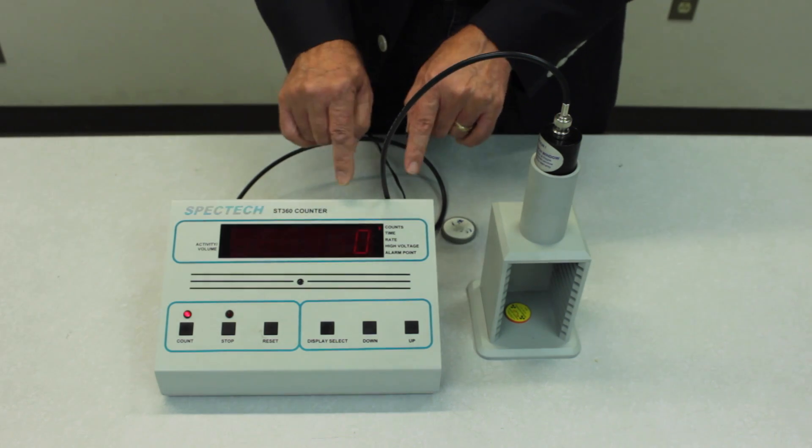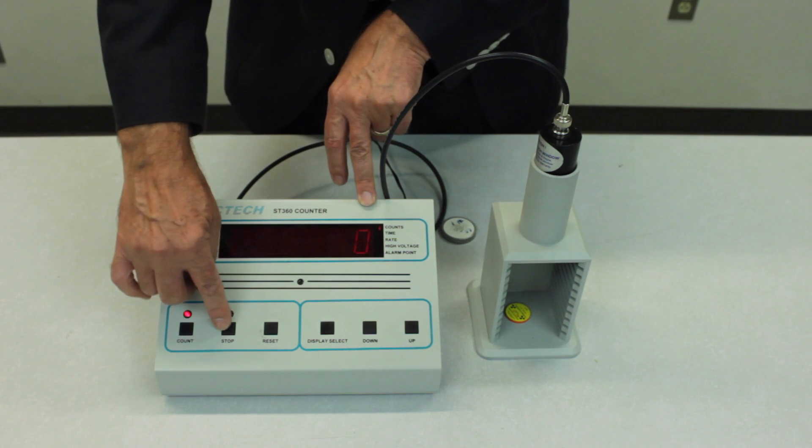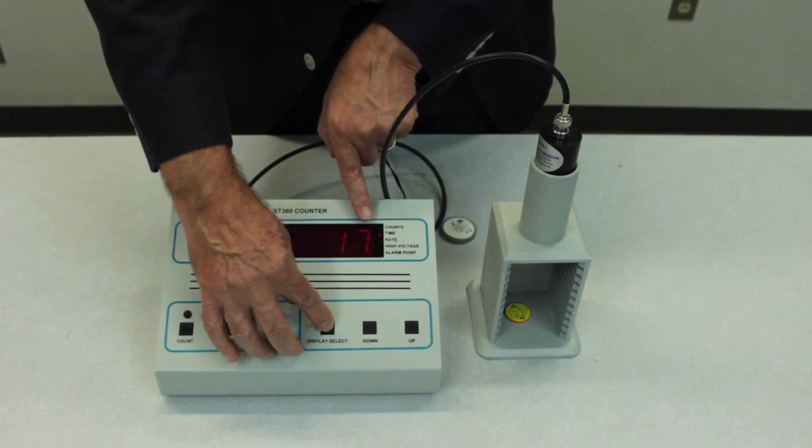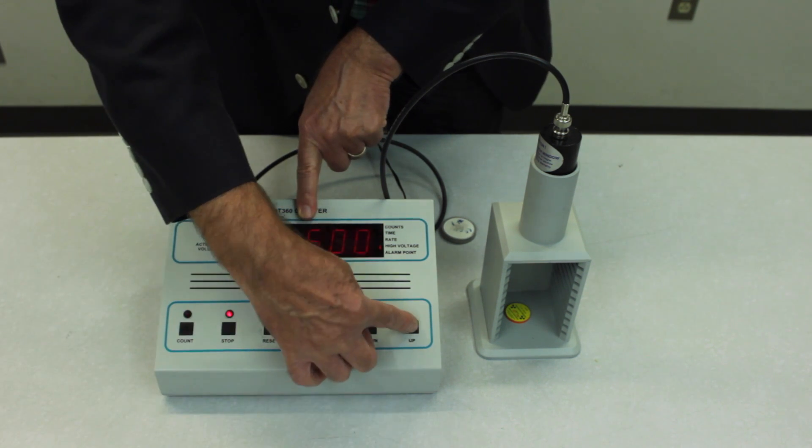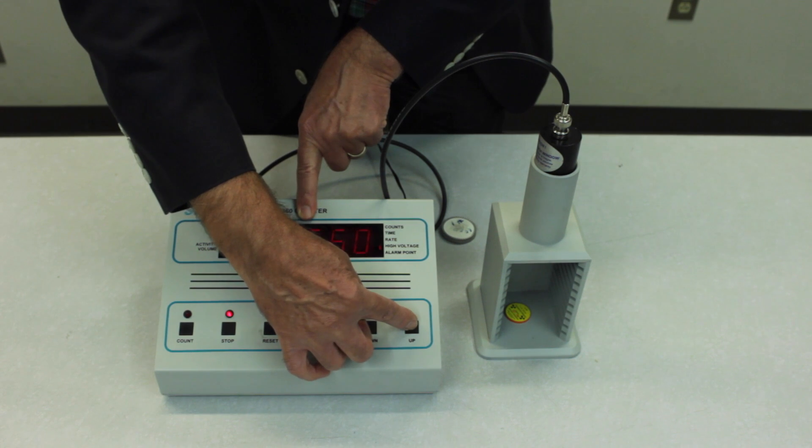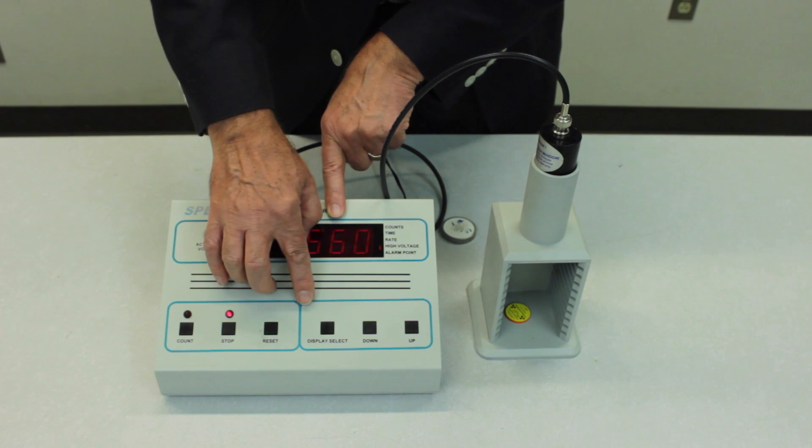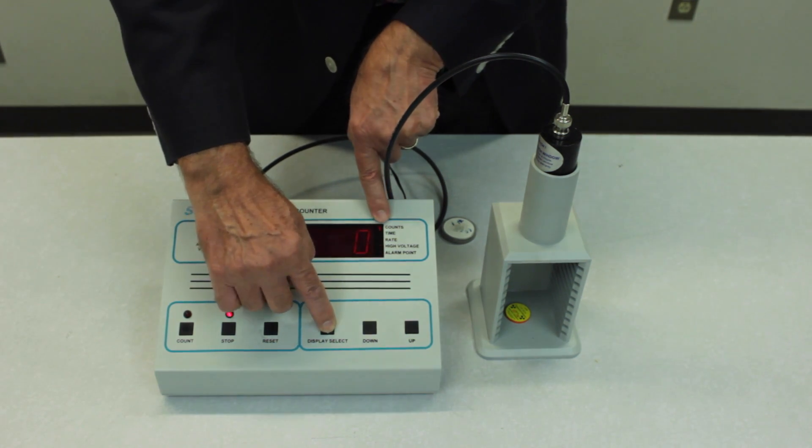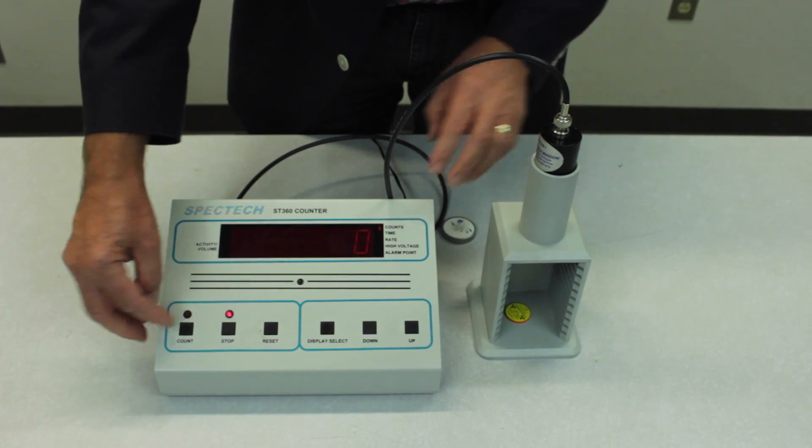So you might want to start around six hundred. And if you're not seeing anything obviously just stop this and declare that to be zero. Set the high voltage again. Let's go up to maybe six hundred and sixty. And we'll see if that's enough to get the counter going. So pressing the display select button again. Back to the count function. And we'll start the count again.